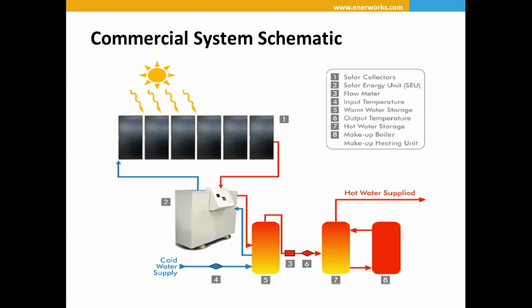And this also simplifies controls. There's no need for complicated controls, because it's a simple inline pass-through system: we heat up what we can, and it passes through to the conventional system. And you always want the fresh cold water for your solar system. If you remember the chart that I showed you from the beginning, regardless of the type of system you're using, they all perform the best if you're using the coldest water. So you want the temperature of the water not to get too hot right away. You can use a higher temperature; we've done systems where you add the heat to a hot water recirc loop. In those cases, you can only use a vacuum tube system, because the temperature of the loop is already so hot that you won't add any heat to it. But in general, for a simple domestic water system, you want to preheat that water coming in.